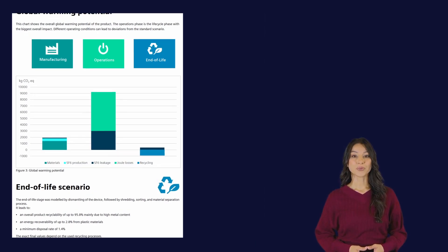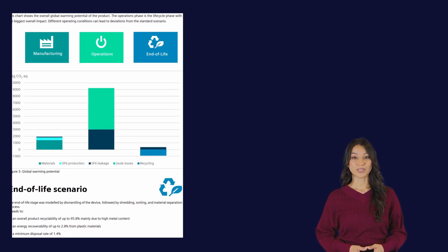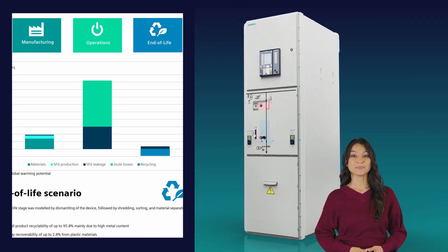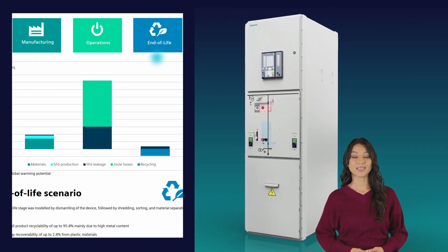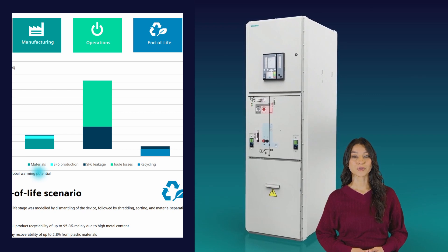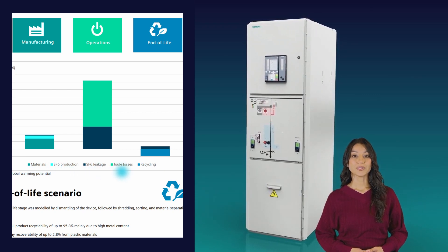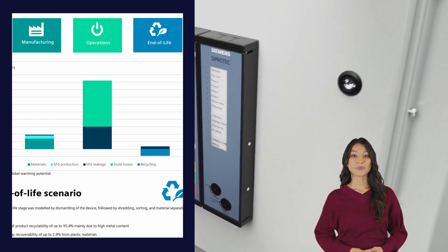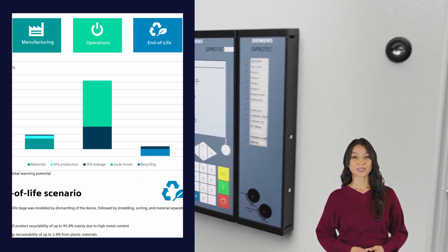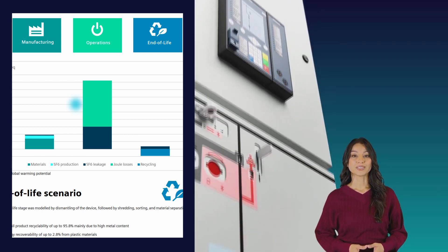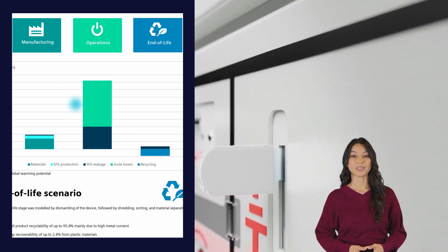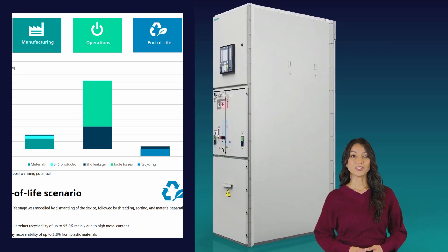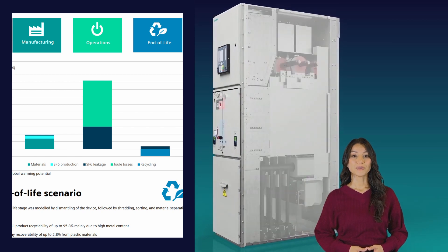Now, we present the global warming potential over the complete life cycle of a typical SF6 gas insulated switchgear separated into three phases — manufacturing, operations, and end-of-life — and then split into five components: materials, SF6 production, SF6 leakage, energy losses, and recycling. Customers can use the chart to see how their decisions can directly influence their own CO2 footprint. For example, using renewable electricity reduces the impact of joule losses to virtually zero. Please remember that the underlying assumptions previously mentioned directly influence this overview of the global warming potential over the lifetime of the product.